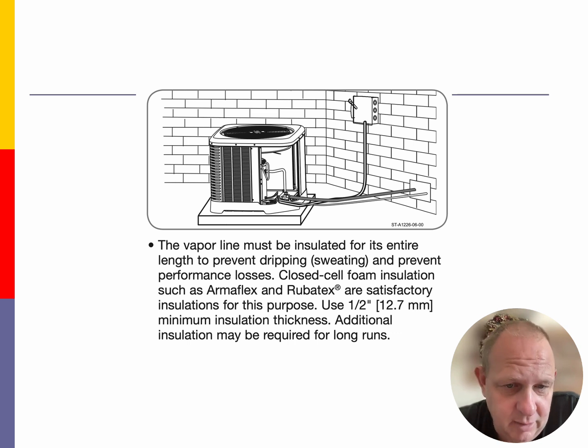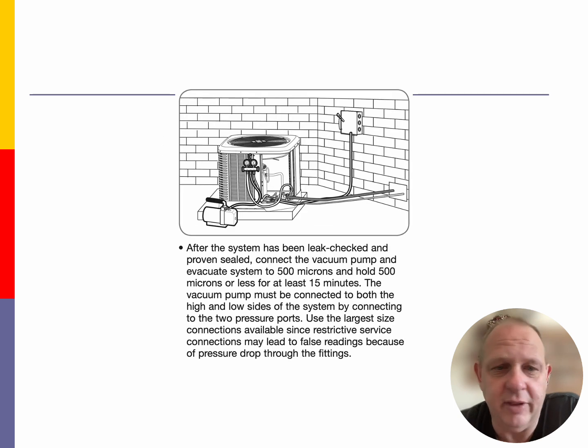After we get done pressure testing the system, checking for a leak, and insulating the lines, we want to pull this thing into a 500 micron setting. Now, different systems out there are going to have you do triple evacuations or nitrogen breaks on the vacuum, and all this is doing is we're trying to drive that moisture out of that line set so that we can have a system that is free of moisture and of air.